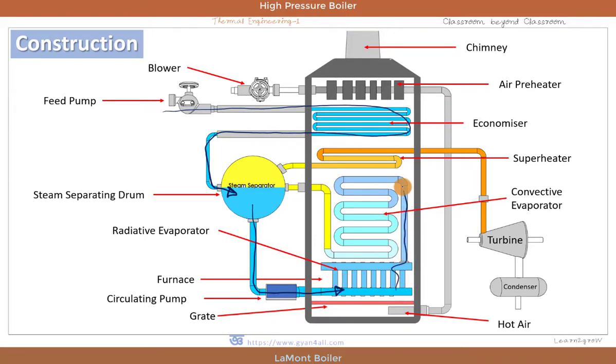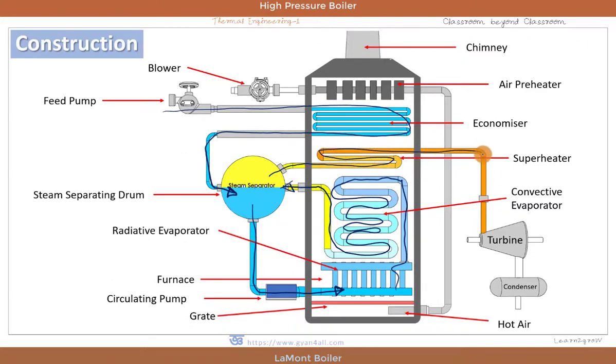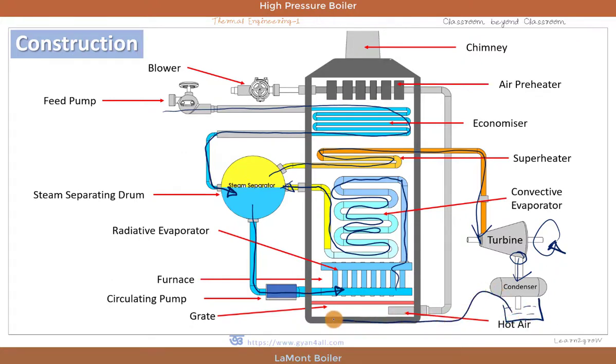From the radiant evaporator, water and steam mixture passes through the evaporative tubes and enters into the steam drum in the form of steam only. The steam then enters into the superheater, and the superheated steam enters into the turbine for production of mechanical energy. The exhaust of the steam turbine enters into the condenser, which condenses the steam into water, and this water can again be used as feed water for the boiler, done by the feed pump.